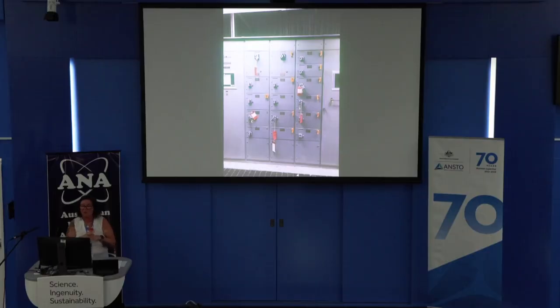So what we do here is have real defense in depth. We start with an operator preparing the work protection, another operator checks it, another applies it, another verifies it, and then maintenance walks it down. If it's a really important work protection, like a large condition guarantee for an outage or a reactor shutdown guarantee, the shift manager walks it down — and that's what I was doing this day. I took these pictures in blues. I was going to walk down a reactor shutdown guarantee on an outage unit, because it's so important to have that extra step of verification when it involves the reactor or a very large isolation.